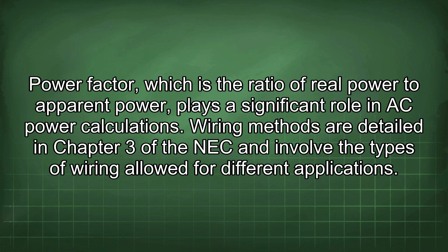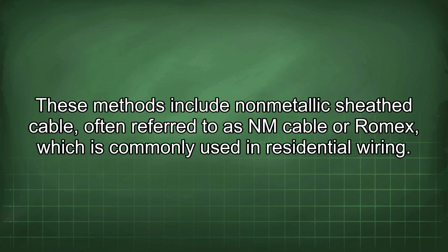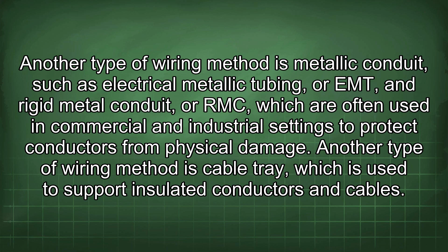Wiring methods are detailed in Chapter 3 of the NEC and involve the types of wiring allowed for different applications. These methods include non-metallic sheath cable, often referred to as NM cable or Romex, which is commonly used in residential wiring. Another type of wiring method is metallic conduit, such as electrical metallic tubing, or EMT, and rigid metal conduit, or RMC, which are often used in commercial and industrial settings to protect conductors from physical damage. Another type of wiring method is cable tray, which is used to support insulated conductors and cables. Each wiring method has specific requirements regarding insulation, support, and allowable uses.